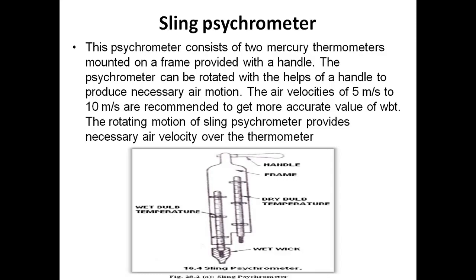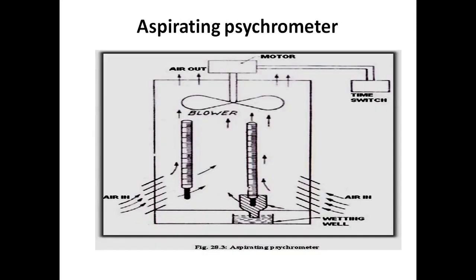A sling psychrometer is used in laboratories. It has a handle with a frame holding a pair of thermometers — one for dry bulb and one for wet bulb temperature — recording simultaneously. The handle is rotated to achieve air velocities in the range of 5 to 10 meters per second through the wet wick. An aspirating psychrometer uses an air blower arrangement to achieve the same recommended velocity range.